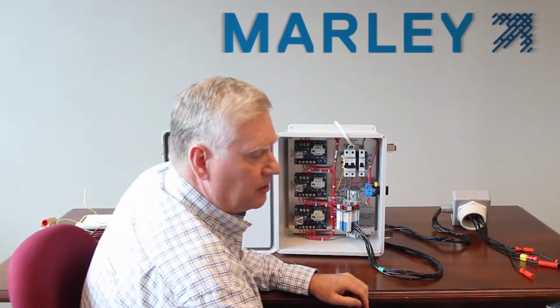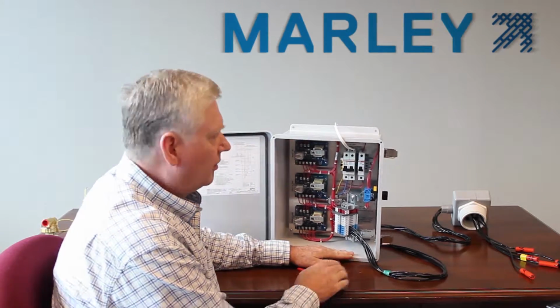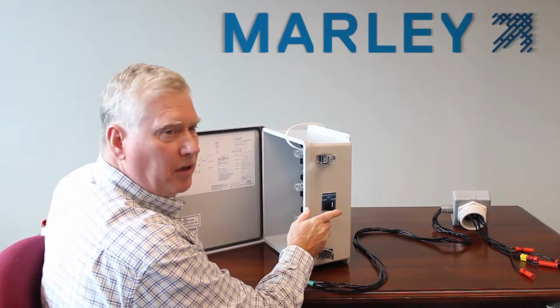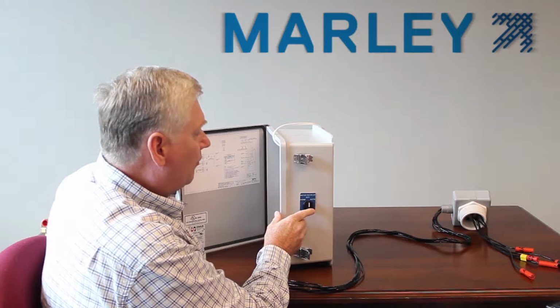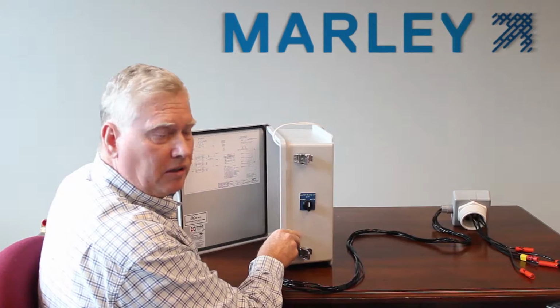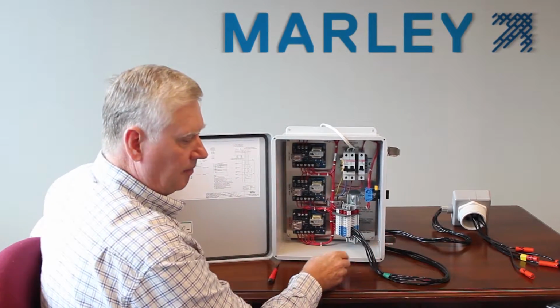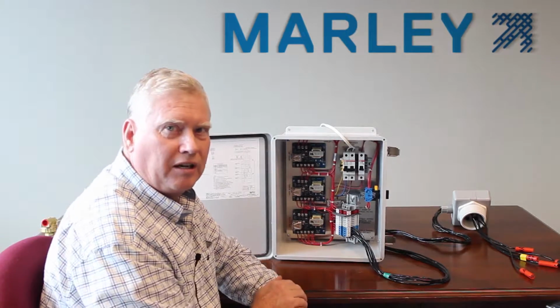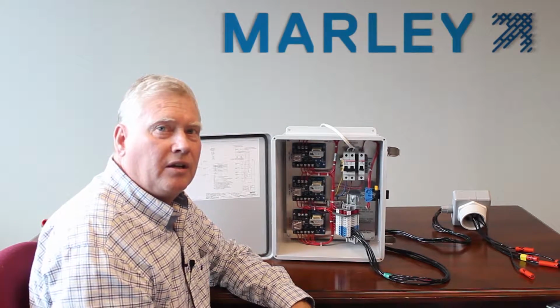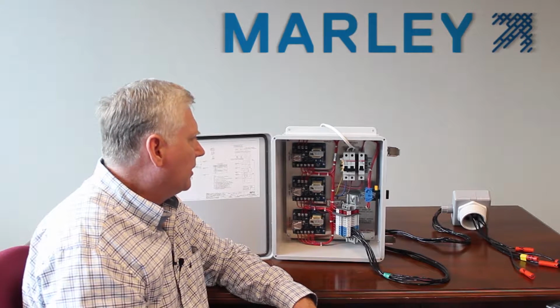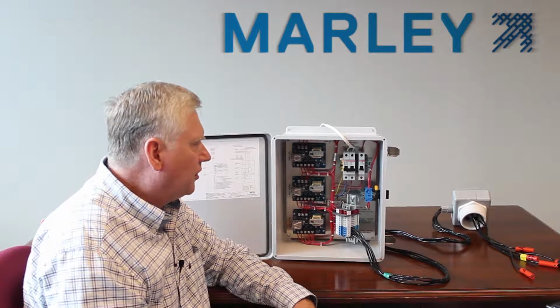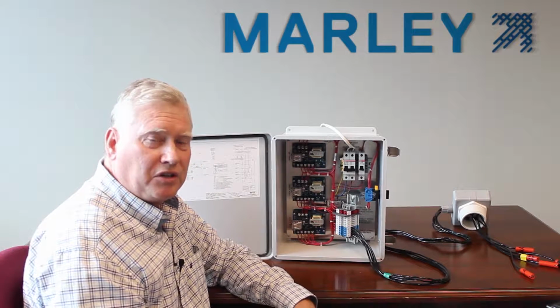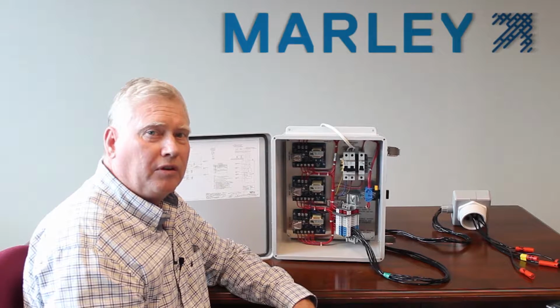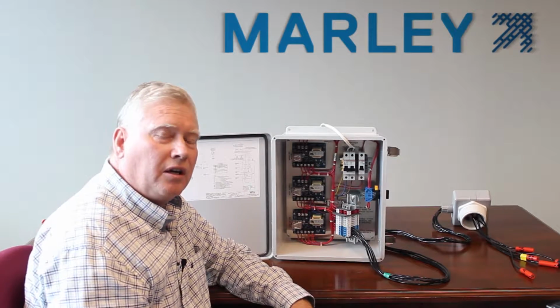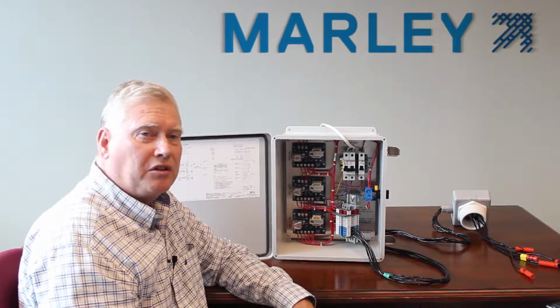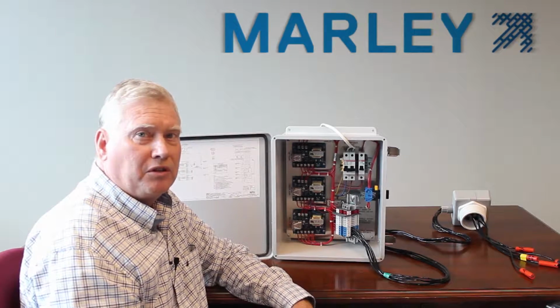One call I get back is that nothing's working on the makeup. There happens to be an HOA selector switch on the side of the panel here, and for it to work in automatic, it has to be in the auto position. If it's in the off position, it's not going to work. And even the simplest thing, like maybe the circuit breakers are not turned on. So when I get a call that it's not working in the field, the first thing I have people do is disconnect the field wiring, and we're going to prove that the control panel itself is functional. Once we do that, we can start chasing things that are outside of the control panel, such as the probes and the solenoid.